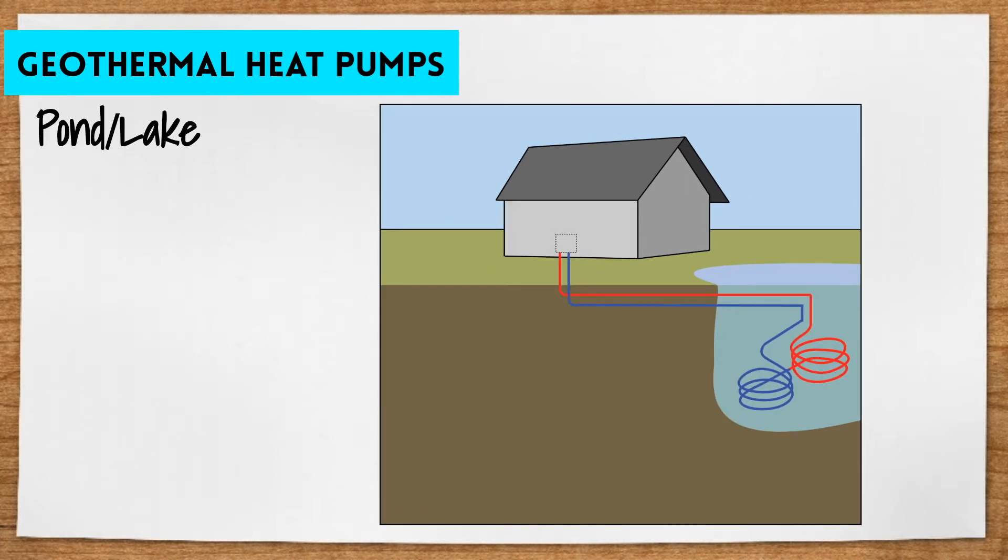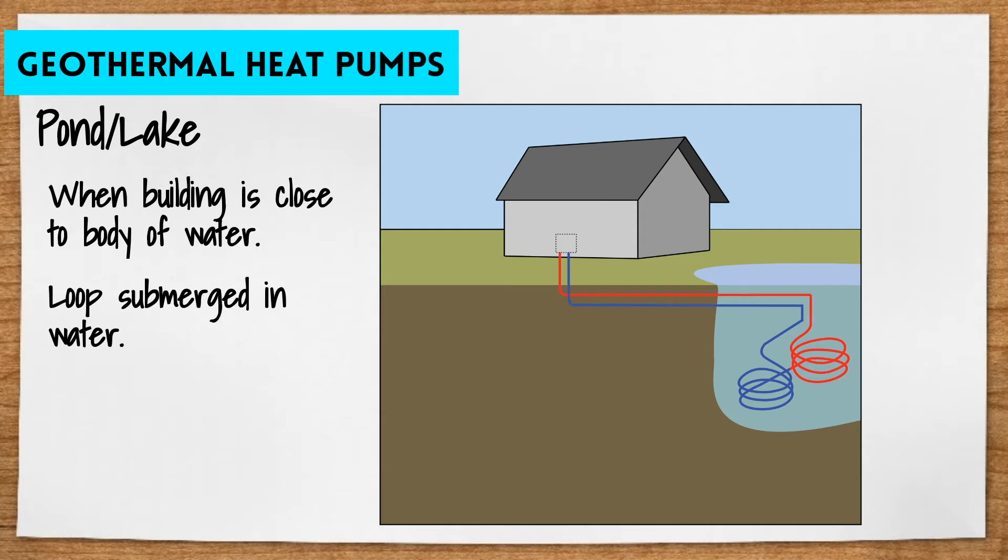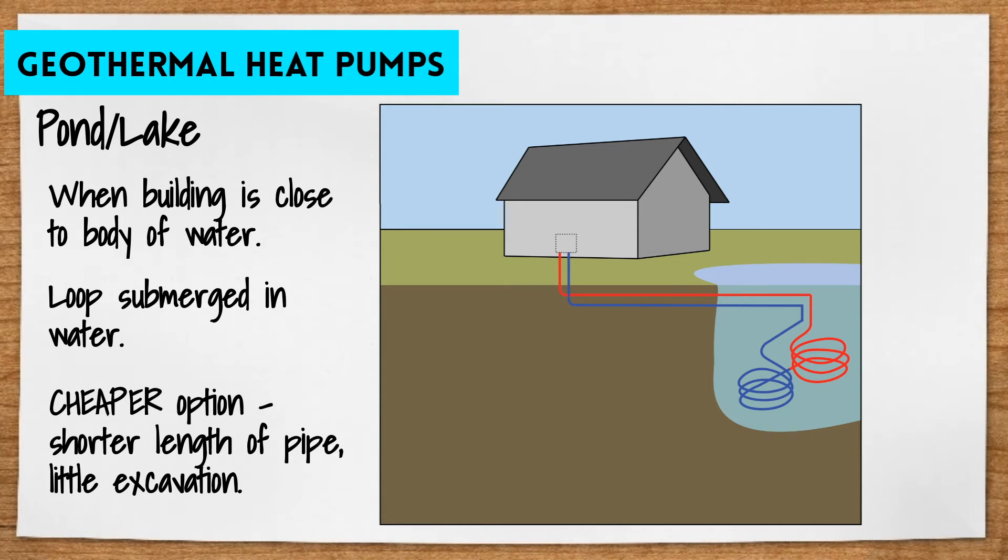The third configuration, pond or lake, can be used when the building is close to a large body of water. The loop is submerged in the water, which will actually conduct heat much faster than the soil. The loop should always remain at least eight feet under the water to prevent freezing. This option requires a much shorter length of pipe and little excavation, making it a much cheaper option if the site can allow for it.